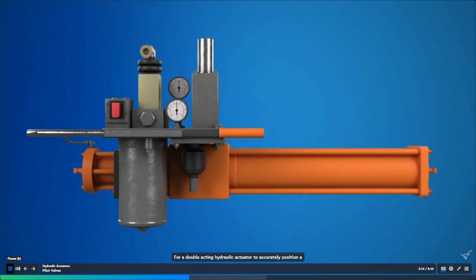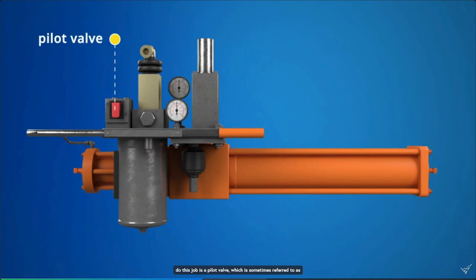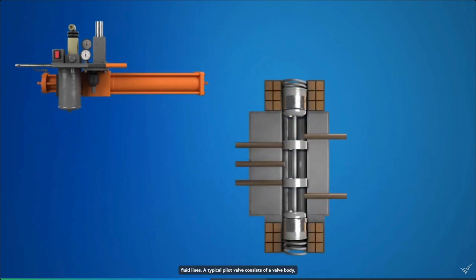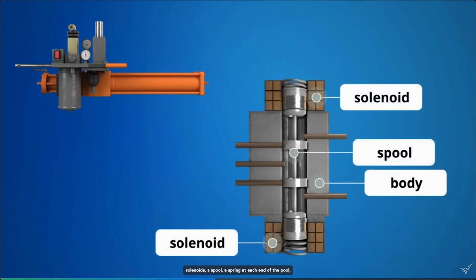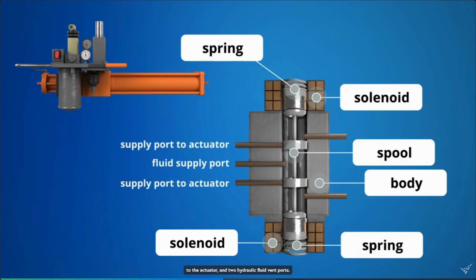For a double-acting hydraulic actuator to accurately position a valve, the amount of fluid fed to and bled from the cylinder must be accurately controlled. The device usually selected to do this job is a pilot valve, which is sometimes referred to as a spool valve. The pilot valve is connected to the actuator by fluid lines. A typical pilot valve consists of a valve body, solenoids, a spool, a spring at each end of the spool, a hydraulic fluid supply port, two hydraulic fluid supply ports to the actuator, and two hydraulic fluid vent ports.